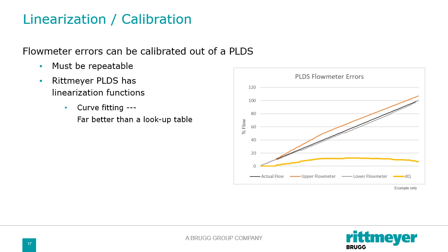Rittmeyer has a very specialized linearization function that does a curve fitting to try and match those curves well, and we can compensate for this almost perfectly, much better than a simple lookup table that we've seen other people do in the field. So this is one of the things that really sets Rittmeyer's PLDS apart from anything else that we've seen out there, and makes ours perform considerably better.